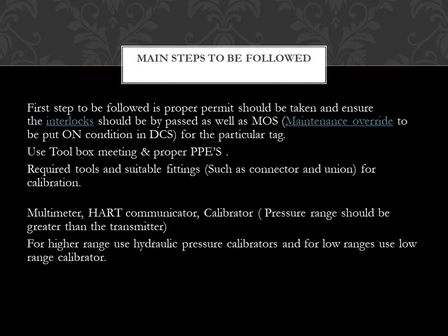Main steps to be followed. First step to be followed: proper permit should be taken and ensure the interlock is bypassed, as well as MOS maintenance override to be put on condition in DCS for the particular tag. Use toolbox meeting and proper PPE.